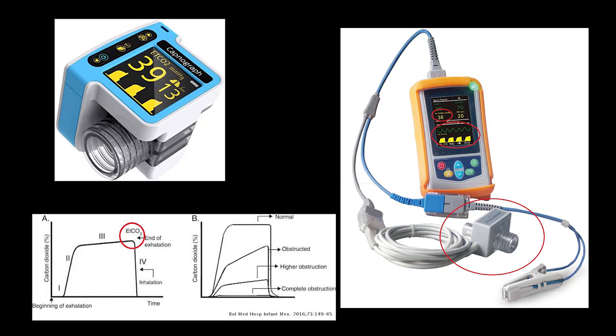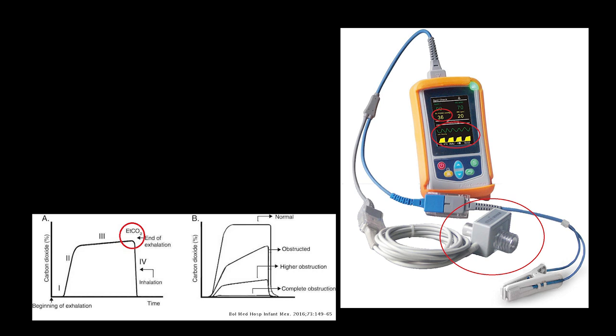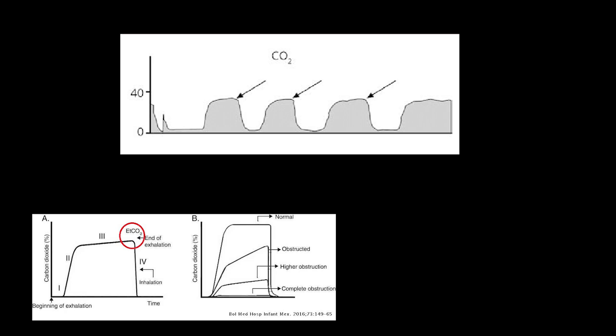End-tidal capnography measures continuous trends in CO2 exhaled by the patient with each and every breath. The capnograph charts the waveform of each breath. As the patient exhales, the wave starts an upward spike, and at the very peak of the exhalation is the end-tidal measurement of CO2, measured in millimeters of mercury. Then, immediately after that, the wave takes a downward stroke as the patient inhales, and the cycle starts all over again.